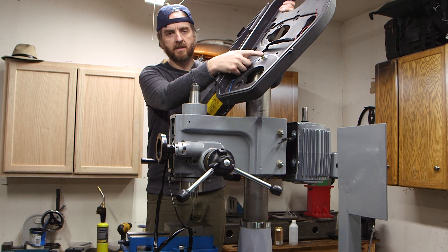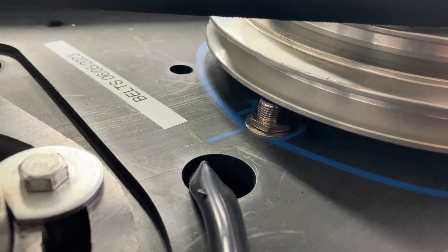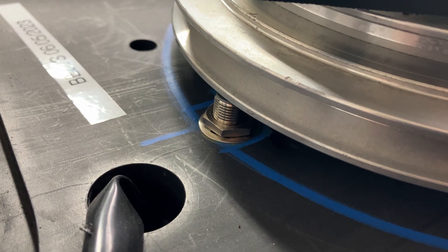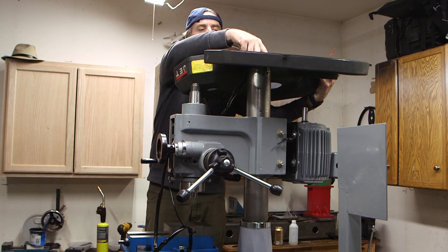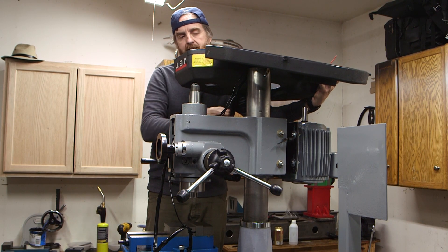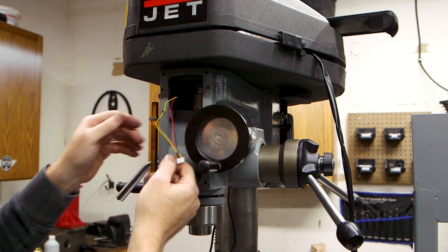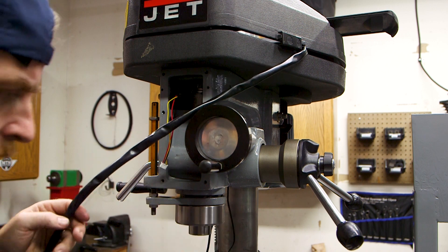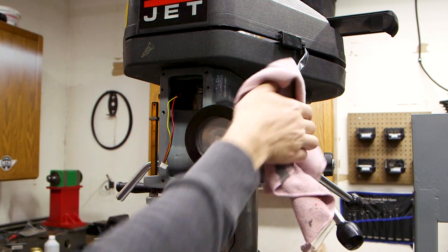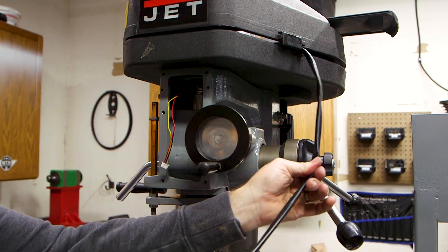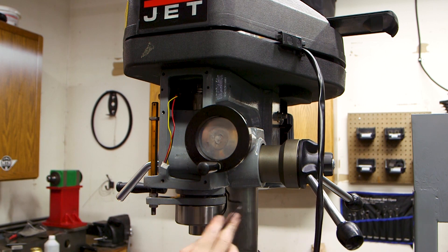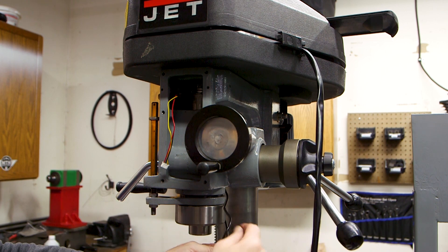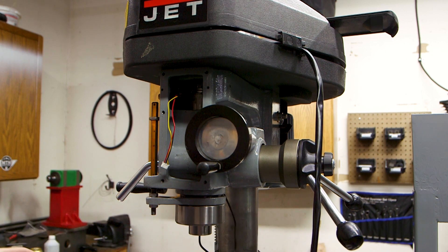I mounted the pickup sensor for the tach inside the belt shroud. I've mounted it in such a way that when the shroud is installed the pickup sensor sits down inside the casting. All right so that's for the tach. The larger wire here this is the power that's going to route back to the power supply in the VFD and the smaller wire is the pickup sensor and I'm just going to coil this zip tight and push it up into the housing.